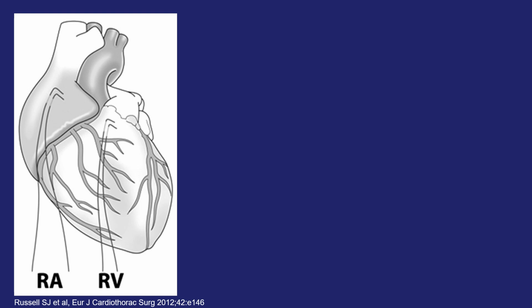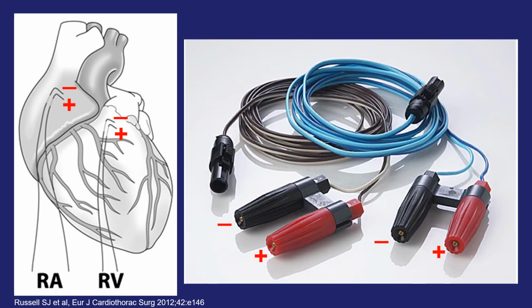Here's a nice cartoon that I like to use to think about epicardial pacing systems, especially when it comes to troubleshooting. You can see here two atrial wires connected to the atrial epicardium and two wires connected to the ventricular epicardium. And when they're connected to the external pacer box, of course, one of these wires will be used as a cathode, the negative pole, and the other used as an anode, and the same thing in the ventricle. Here's just another image of one type of connector, and I'll show in the next slide how these are connected to the epicardial wires. But here you can see the ends that plug into the external pacer box and these screw type connectors that connect to the little pins after the sharp needles are broken off in the operating room.